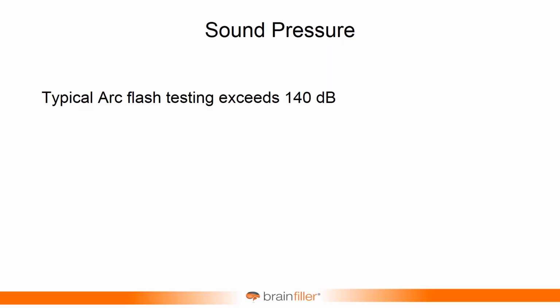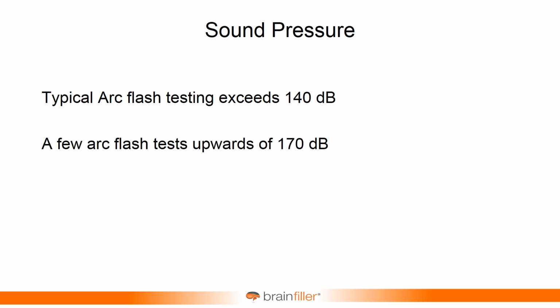And with an arc flash, we've had some measurements. In a typical arc flash, the sound level is about 140 dB. I mean, it's an impact. It's not sustained. But 140 dB could cause some hearing damage. And some tests have actually recorded the sound pressure upwards of about 170 dB. That could just destroy your ears. So sound pressure is very significant, and wearing hearing protection is why. And so we have some more data, some more tests to support what can actually happen during an arc flash.